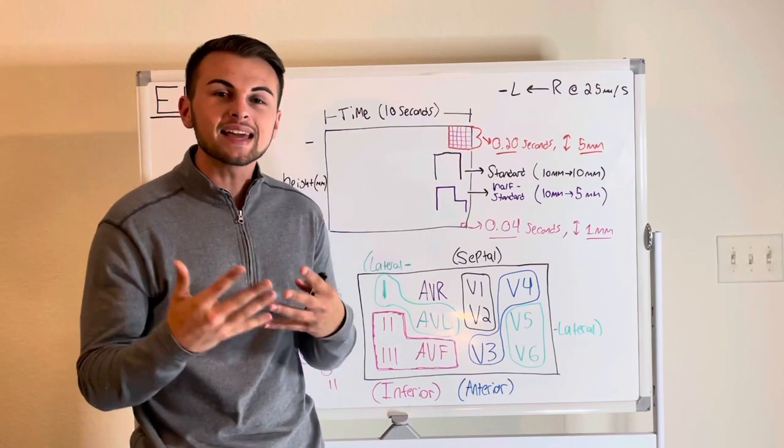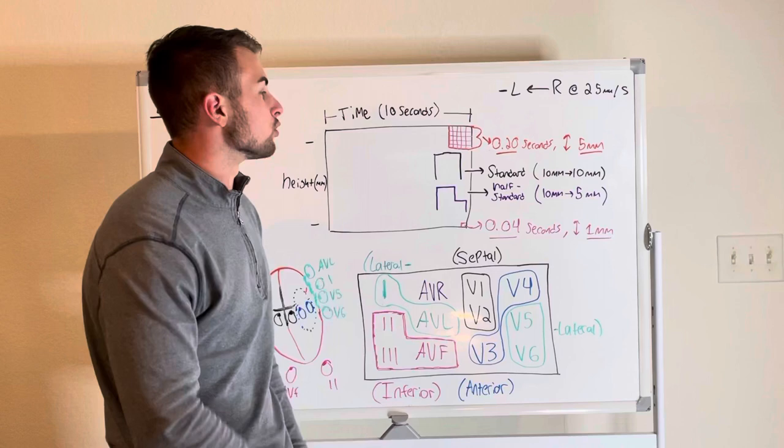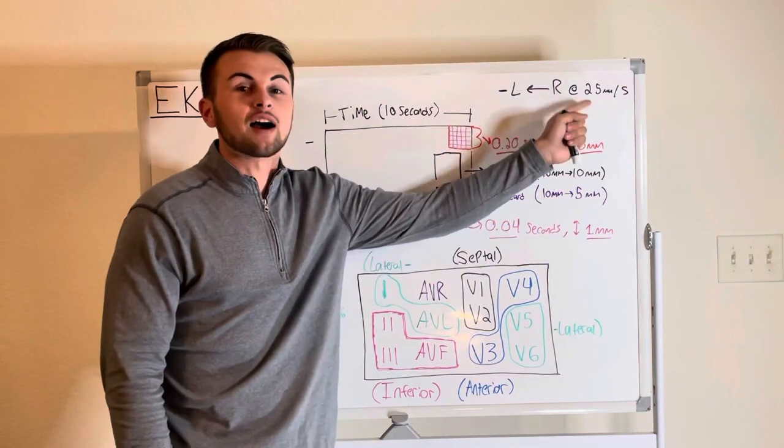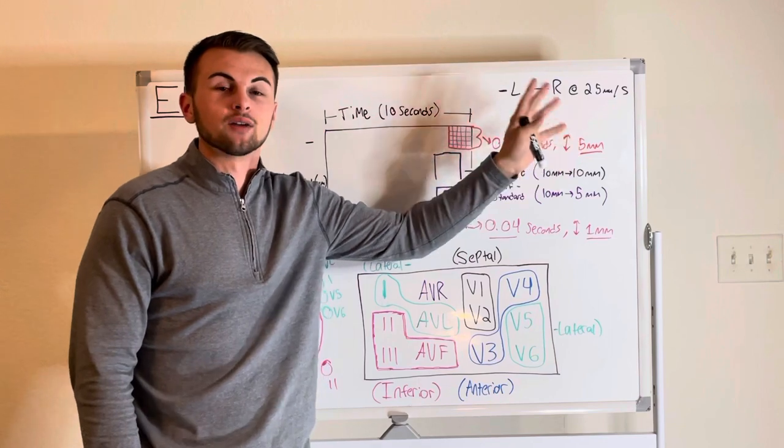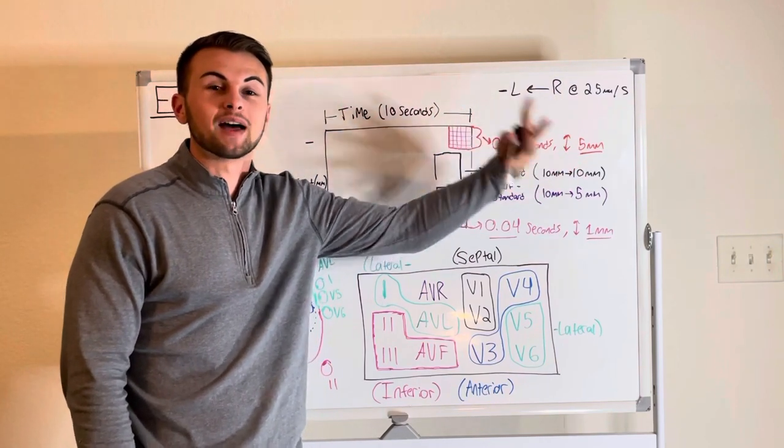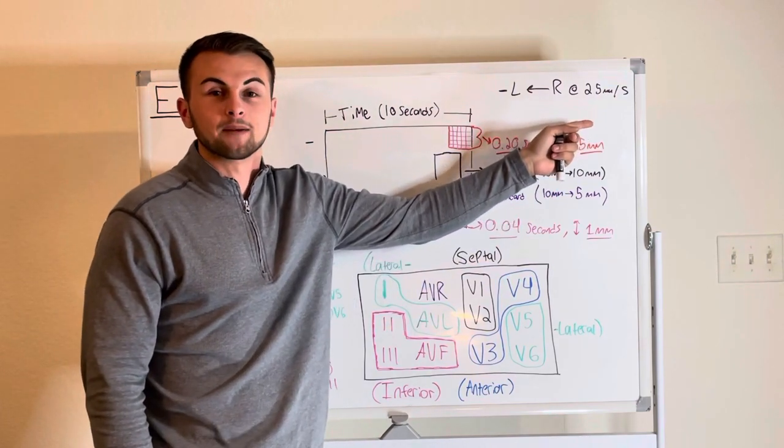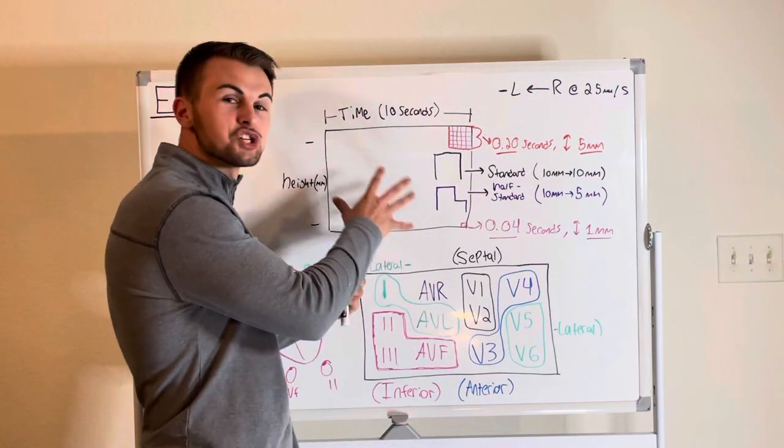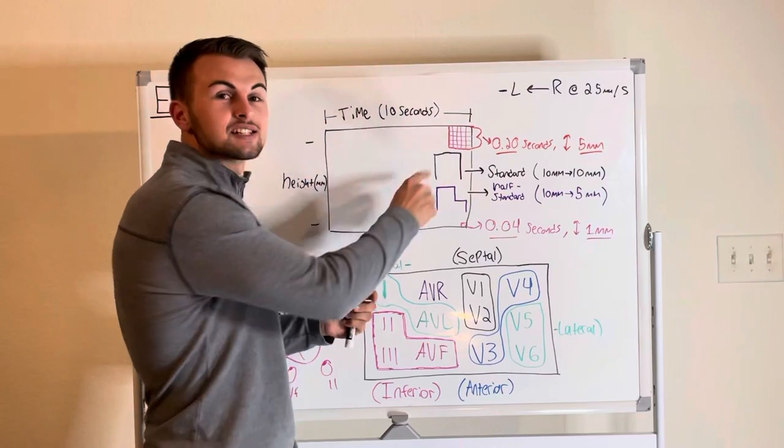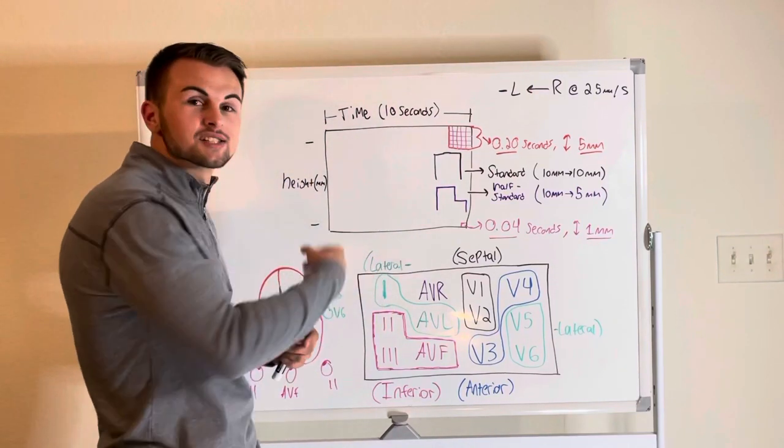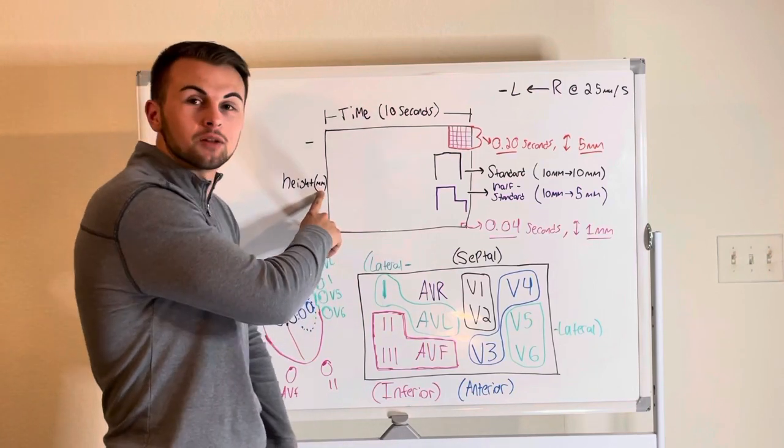First, the EKG machine paper travels from right to left at a rate of 25 millimeters per second. This is important because if somebody were to mess with the configurations you need to remember to set it back to 25 millimeters per second. Also on our EKG sheet the x-axis represents time in seconds while the y-axis represents height in millimeters.